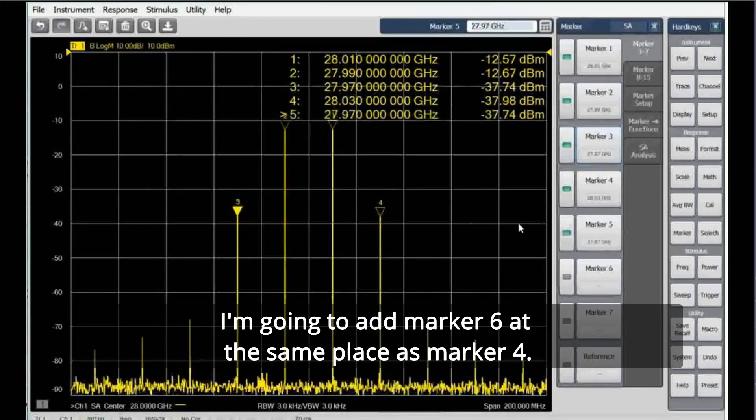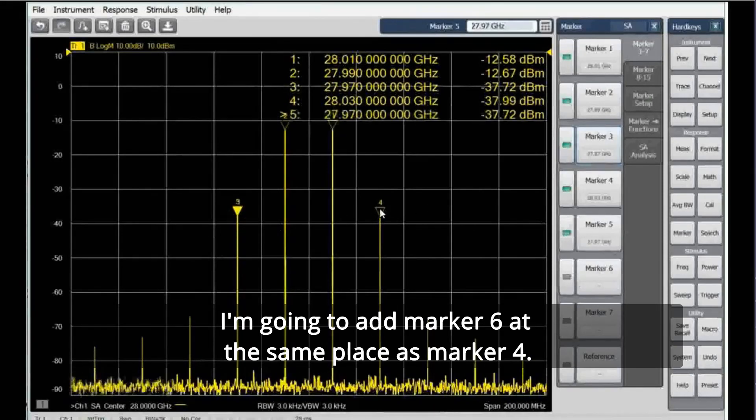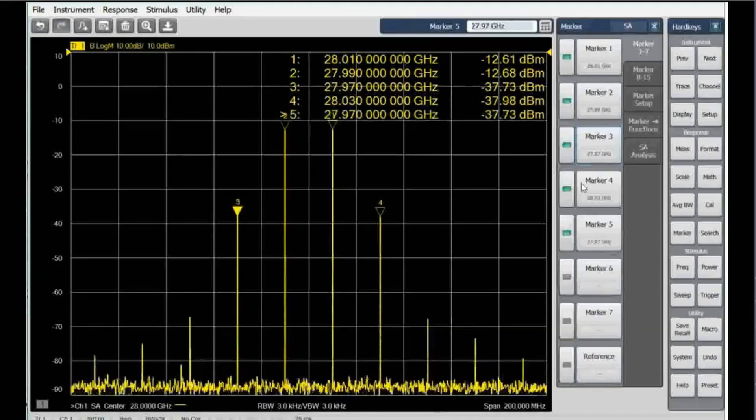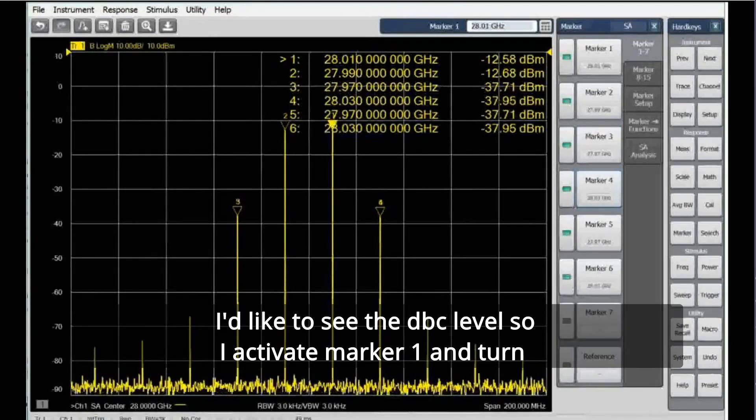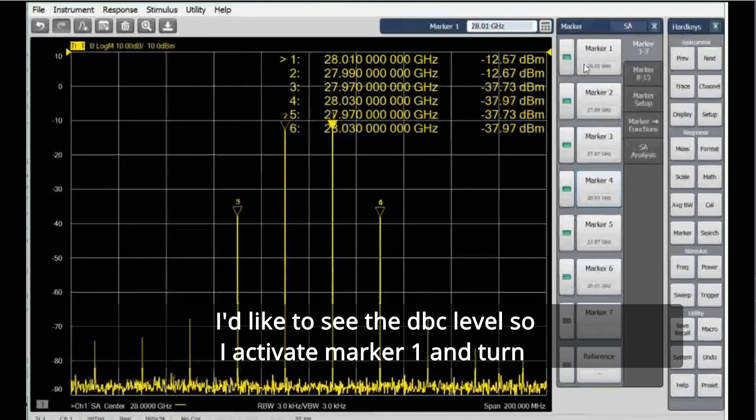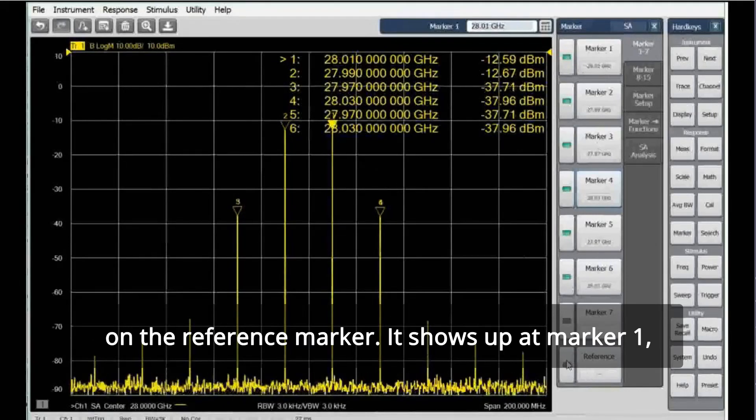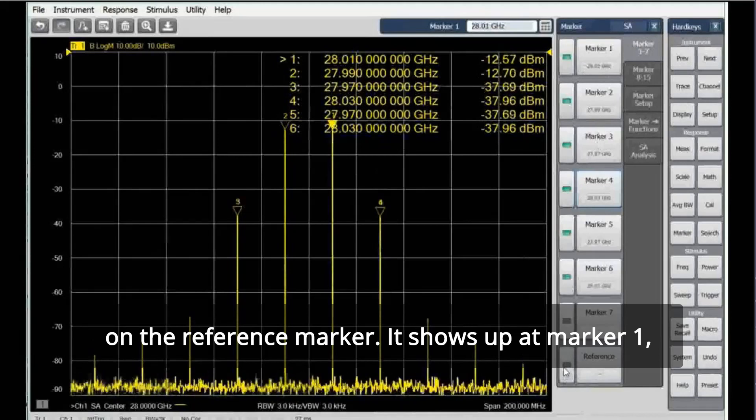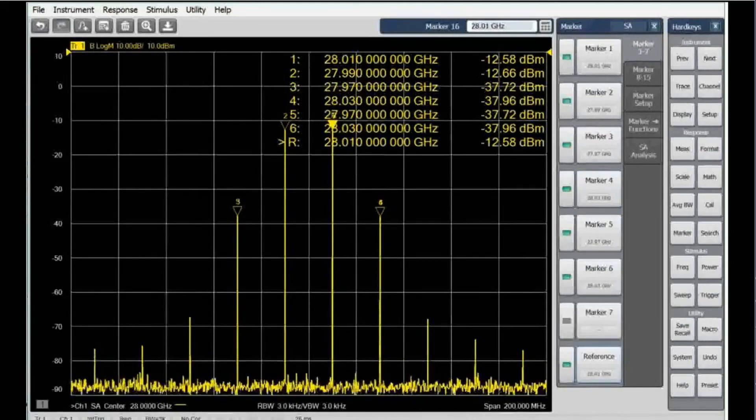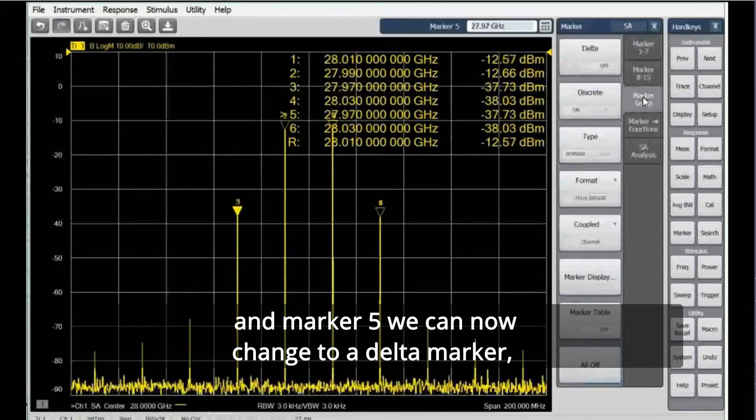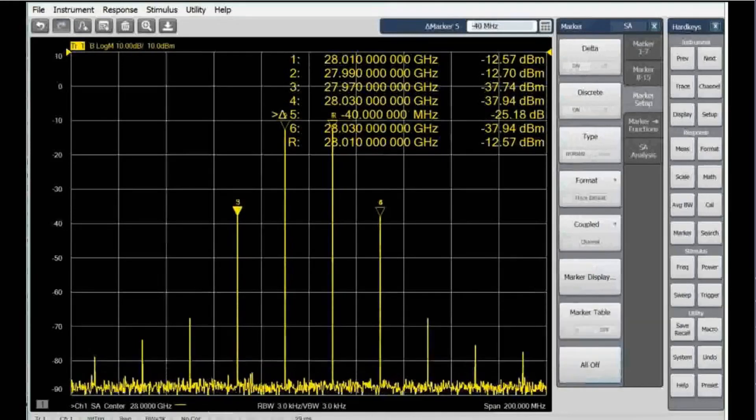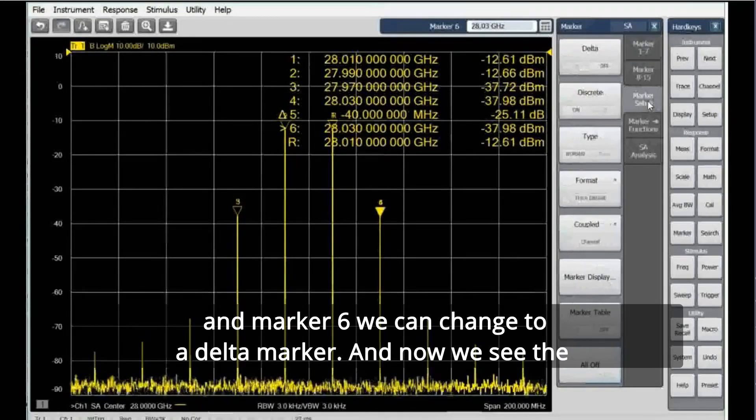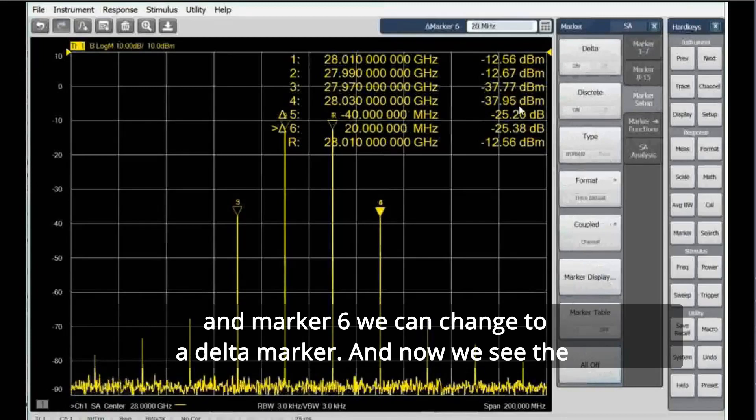I'd like to see the dBc level, so I activate marker 1 and turn on the reference marker. It shows up at marker 1, and marker 5 we can now change to a delta marker, and marker 6 we can change to a delta marker.